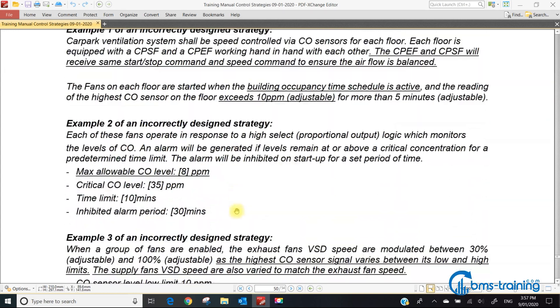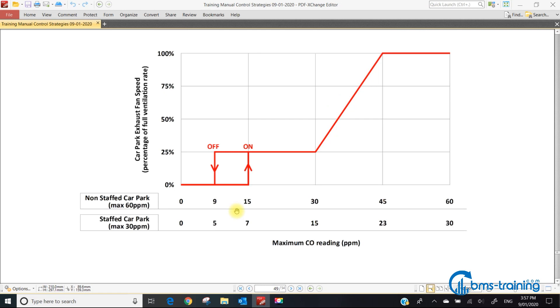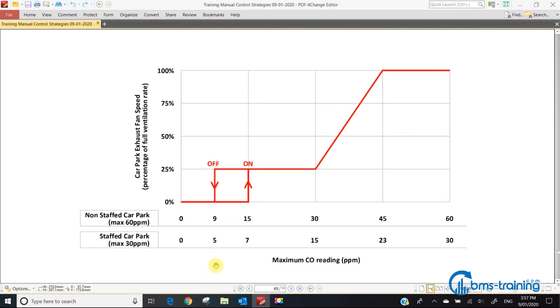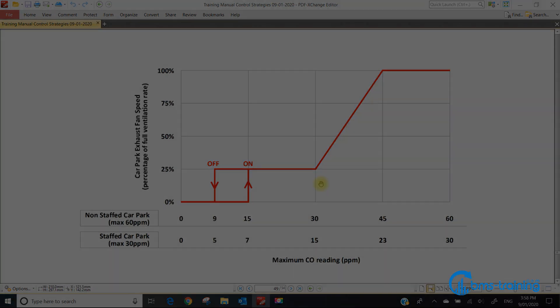That transfer function is the simplest thing in the world, but it is very seldom programmed correctly in the BMS. When I do witnessing and go to site, 50 to 80% of the time this will be wrong. Sometimes the FD has the words non-staffed and staffed car park and talks about exposure limits, but I still see these values being mixed up. This is an easy one to fix. If you learned something, please like and subscribe.